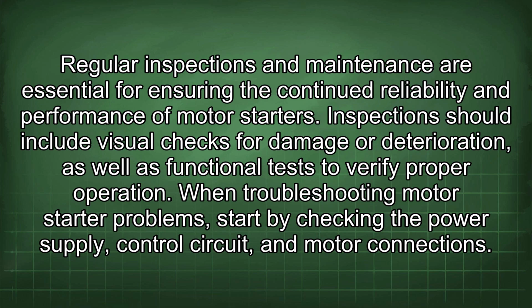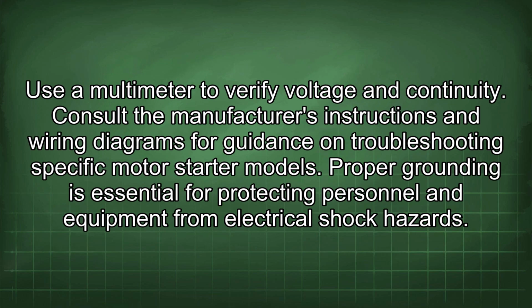Inspections should include visual checks for damage or deterioration, as well as functional tests to verify proper operation. When troubleshooting motor starter problems, start by checking the power supply, control circuit, and motor connections. Use a multimeter to verify voltage and continuity. Consult the manufacturer's instructions and wiring diagrams for guidance on troubleshooting specific motor starter models.